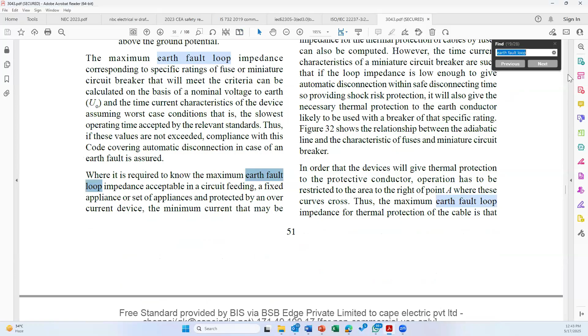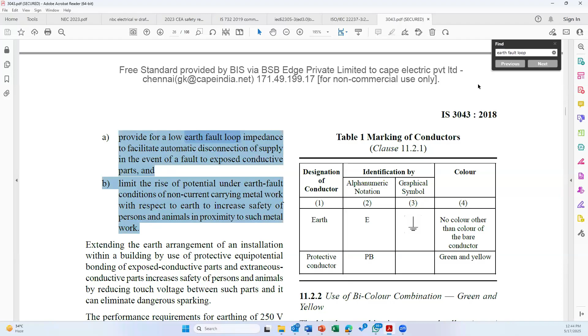So this one, the purpose of earthing is what is written in this particular clause. The purpose of earthing is to provide a low earth fault loop impedance to facilitate automatic disconnection of supply in the event of a fault to exposed conductive parts, and to limit the rise of potential under earth fault condition of non-current carrying metal work with respect to earth, to increase safety of persons and animals. So these two are the requirements of earthing, which is existing since 1966.